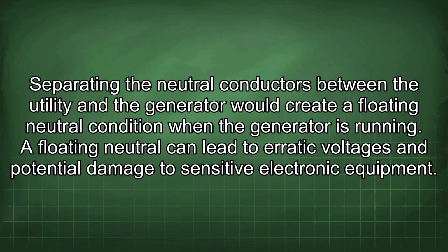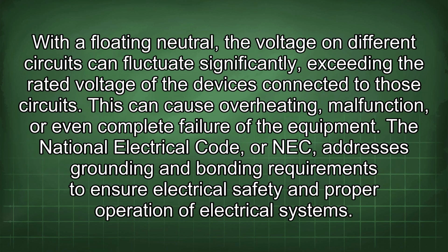Separating the neutral conductors between the utility and the generator would create a floating neutral condition when the generator is running. A floating neutral can lead to erratic voltages and potential damage to sensitive electronic equipment. With a floating neutral, the voltage on different circuits can fluctuate significantly, exceeding the rated voltage of the devices connected to those circuits. This can cause overheating, malfunction, or even complete failure of the equipment.